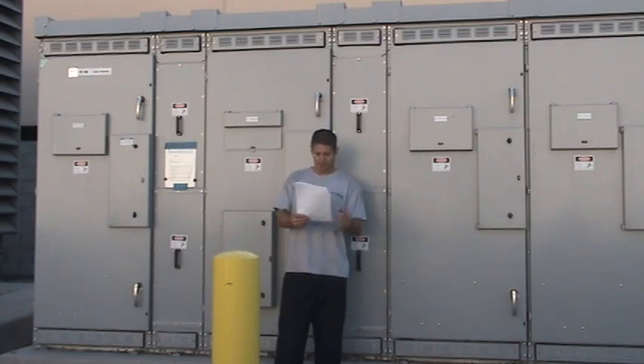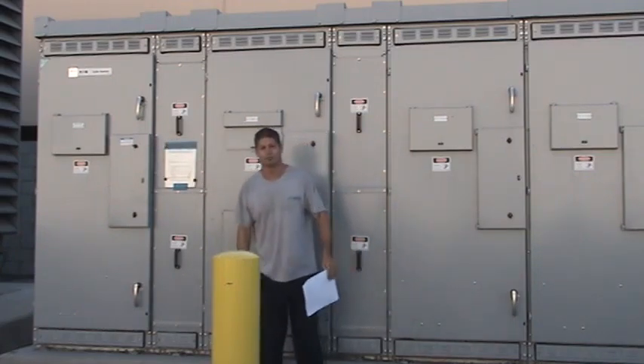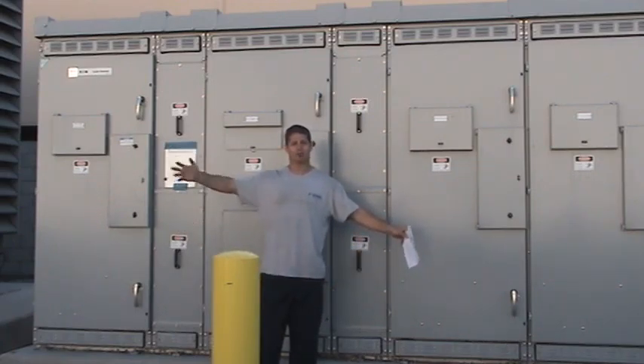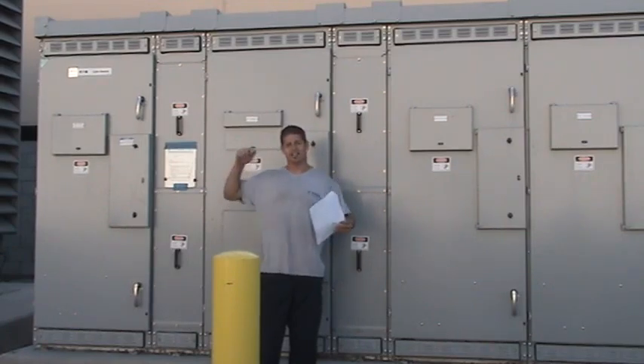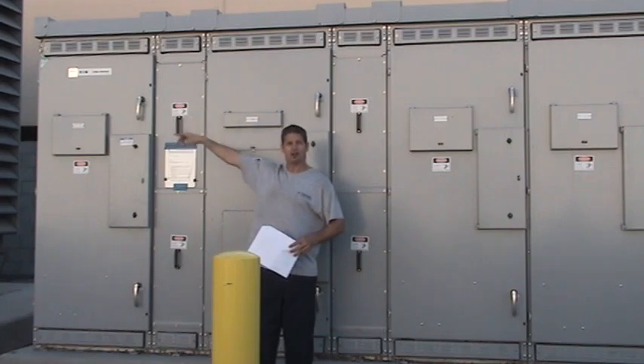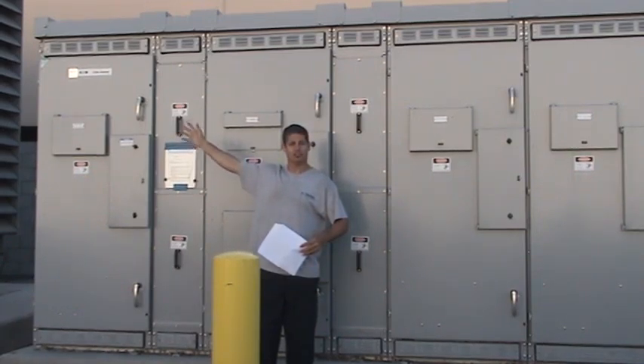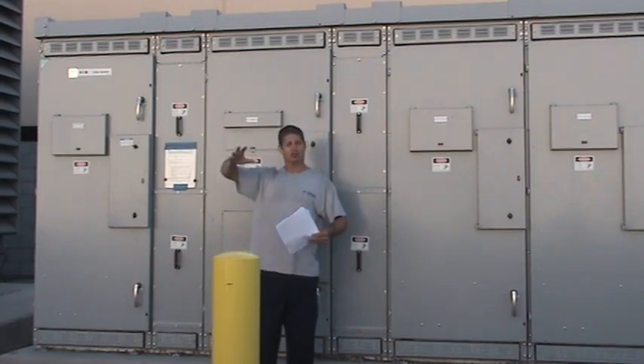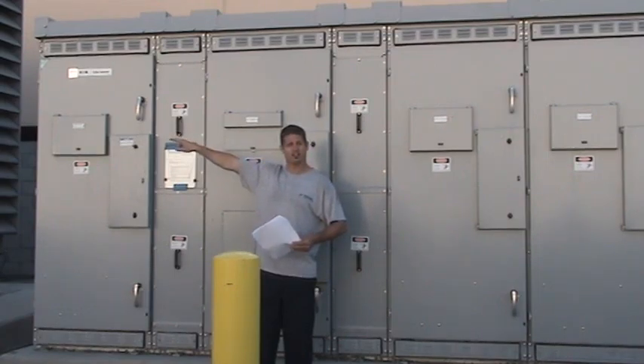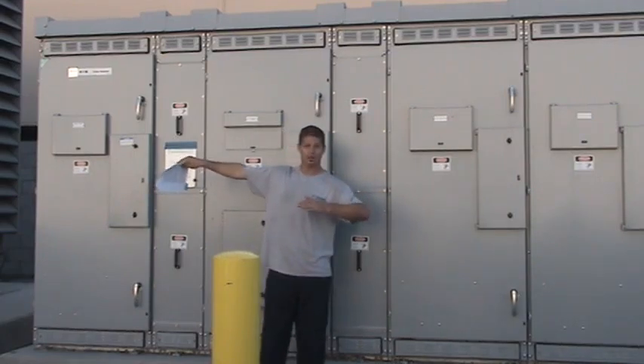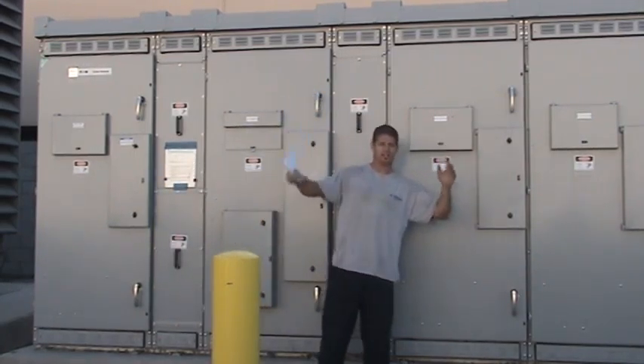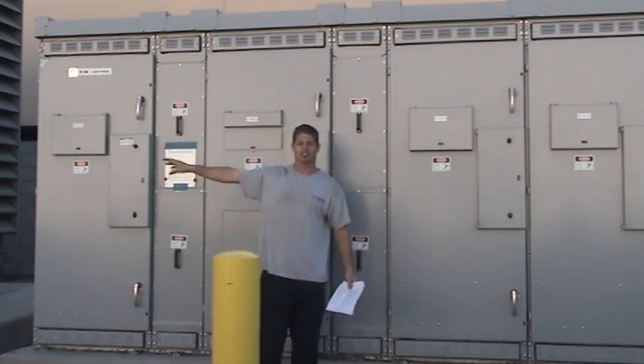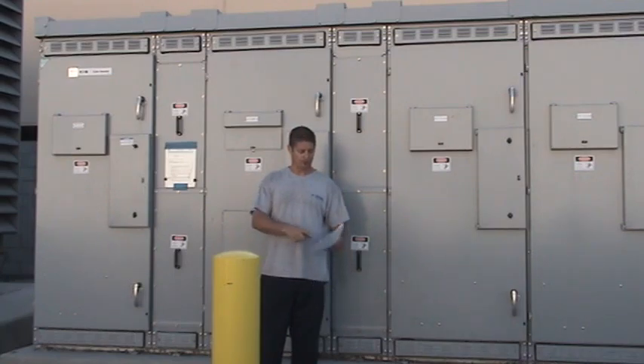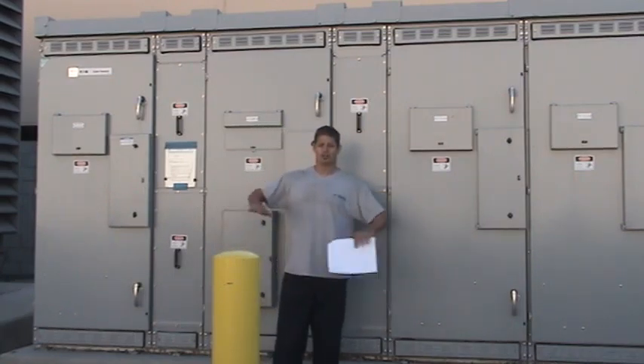So then it sends the close signal to the generator breaker, and you're on generated power. Now you're running on generated power, and then it'll back out of that. Anytime that power is received on your normal, let's say it's Edison power, your supply voltage at RP4, it'll start the sequence to back out, and it will initiate the shutdown for the generator. The breaker over here will now open. The mains will close again, and you're back on normal power, and the generator will continue down its shutdown process. All right? So basically, that's the functionality per this sequence of operations for the normal operation of the switchgear.